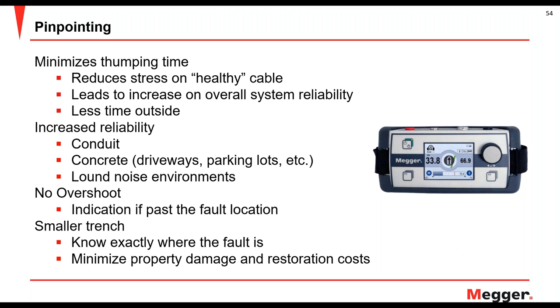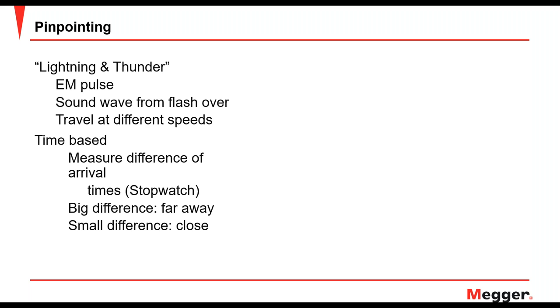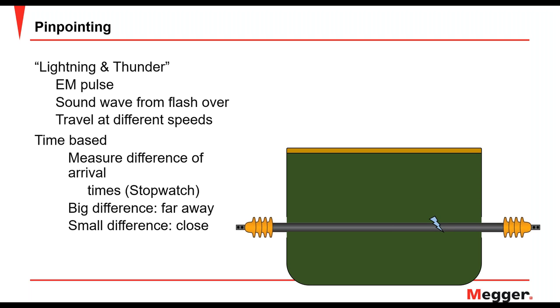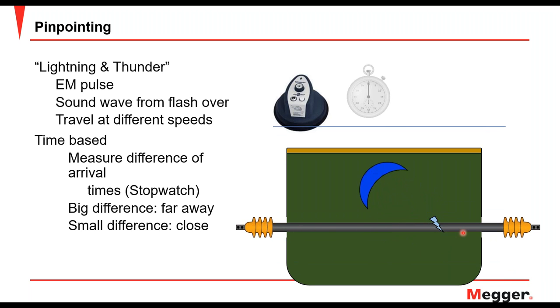So you have your fault right here, and as soon as the equipment reads the electromagnetic pulse on there it starts a timer, and then as soon as the acoustic hit arrives, it gives you the actual calculation of where the actual fault is. So if you're walking above ground and it's telling you the fault is 10 feet, then you walk a little and it's 5 feet, then it goes back to 10 feet — you know you passed it, walk back 5 feet. It's telling you 5 feet because it's 5 feet underneath you — but that doesn't mean get a backhoe and try to get the whole five feet in one scoop.